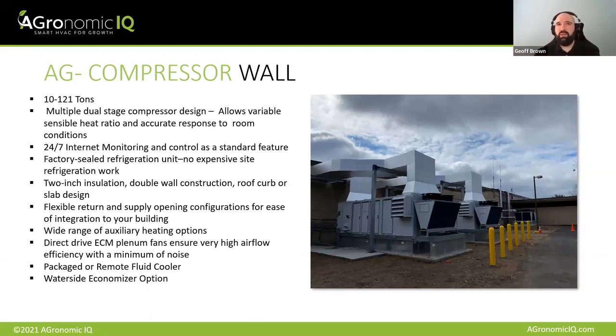And so when I say high enthalpy environment, again, one of the challenges with standard rooftop equipment is you've got a box on the roof. And if you turn that box off and it's not designed for it, well, that box is going to get wet, because the box is going to be cold, there's no air flowing through it, and you're going to have condensation problems in it. And again, this is one of the challenges with on-off control of typical HVAC, is you end up with a bunch of other problems that come out of it. So again, this is typically how we would apply equipment to a facility.